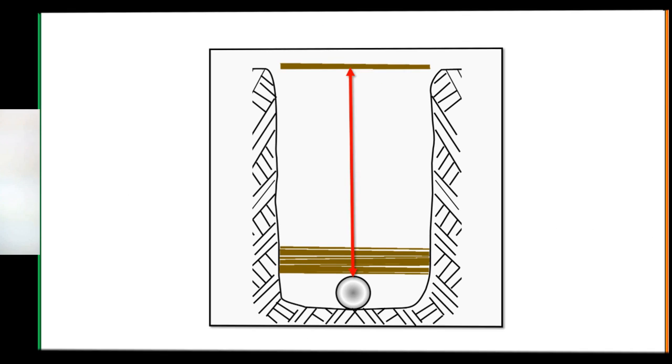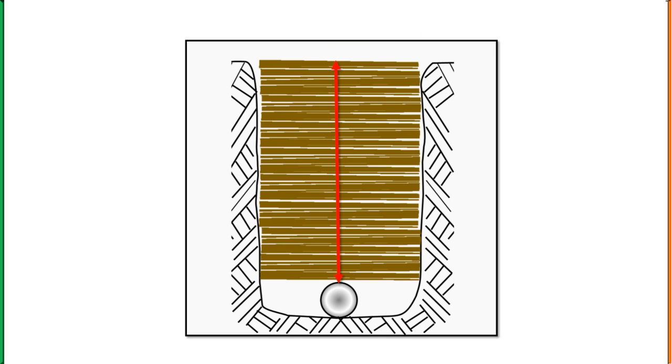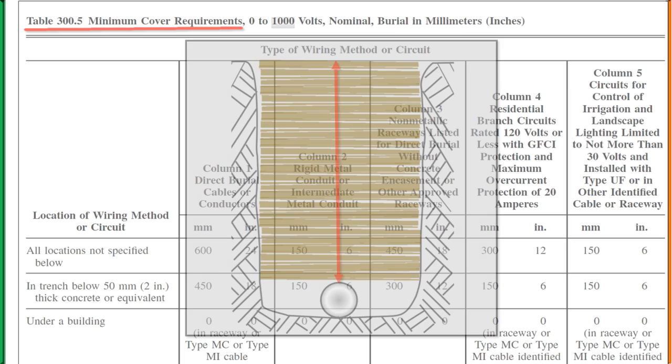This right here is cover over the top of that pipe. When we dig a ditch or trench and put our pipe in it, this is our cover from the top of the pipe to finish grade. You might need to bury your pipe deeper than you would normally think in order to get your minimum cover requirements over the top of the pipe. And that's what this table applies to.